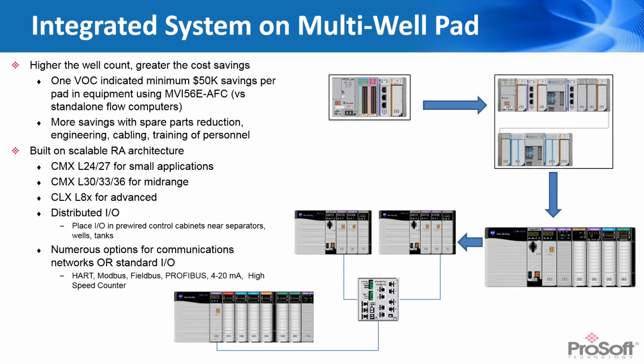That's just in equipment alone. When you start to factor in additional savings realized through spare parts reduction, engineering, cabling - the use of distributed I/O locally, right at your separators, wellheads, and tank batteries - you reduce home-running cables all the way back to your control house. Really only having to run power and an Ethernet cable to those locations can be beneficial for commissioning time, cabling reduction, and makes the system easier to troubleshoot.